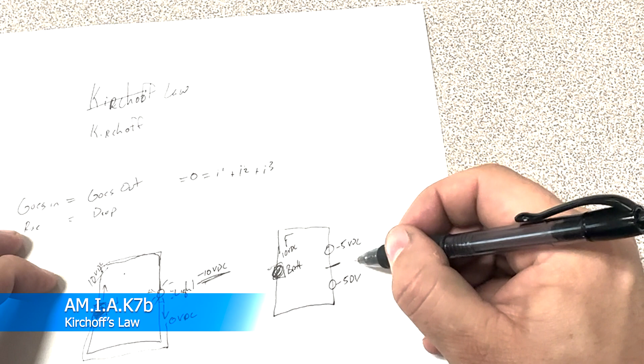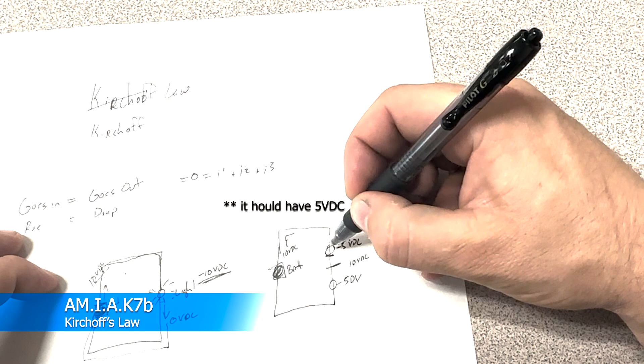If I'm trying to troubleshoot why these lights aren't dimming properly or why one is out, I want to take my meter and check right here. If we know we're putting 10 volts DC in and it's going around, it should still be 10 volts DC right here. If it's anything less than that, I know there's extra resistance in this light. If it's anything more than that, I know this light bulb is probably not doing what it's supposed to, and we need to change it, or maybe the connector here or here is corroded, broken, or somehow not right.